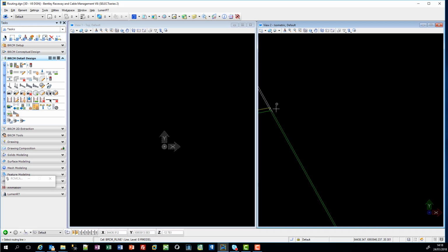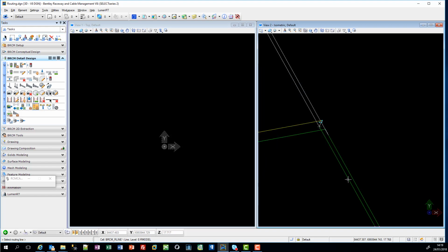And if there is a yellow one, see here, there is one cable in and here's the spare only 32%. So that's also maybe the reason you see only one cable routed inside, because it's not enough spare to route a second cable with same dimension, for example. And it shows here for each, so that's the control part and the other part is the low voltage part.